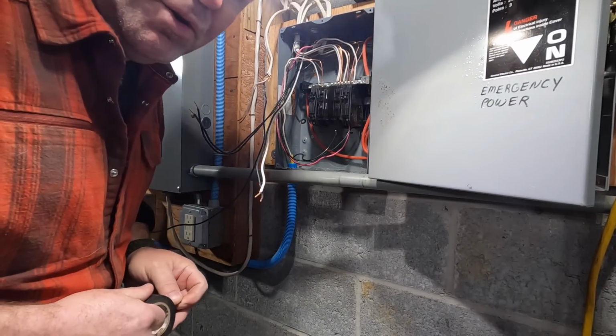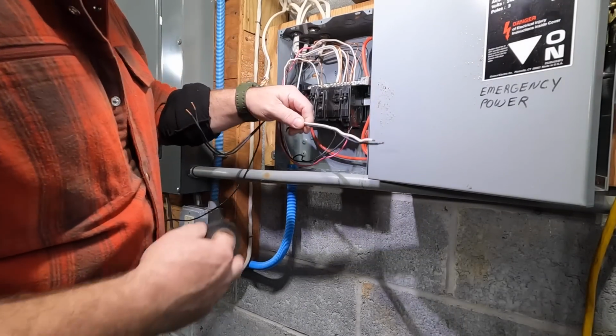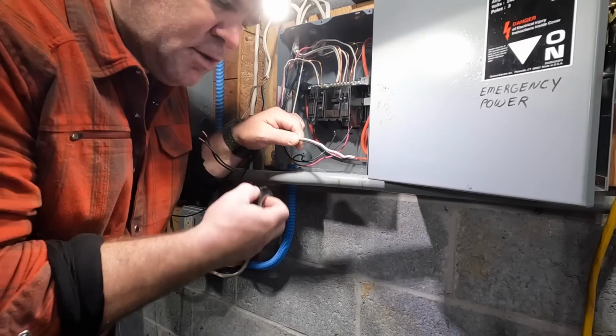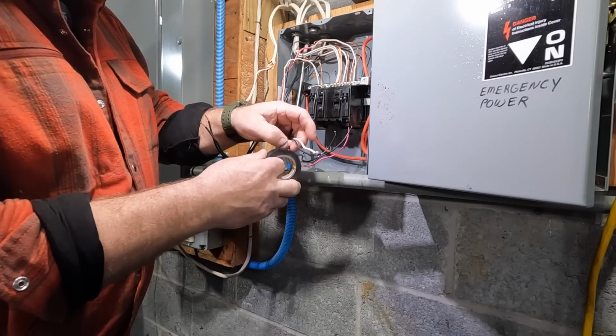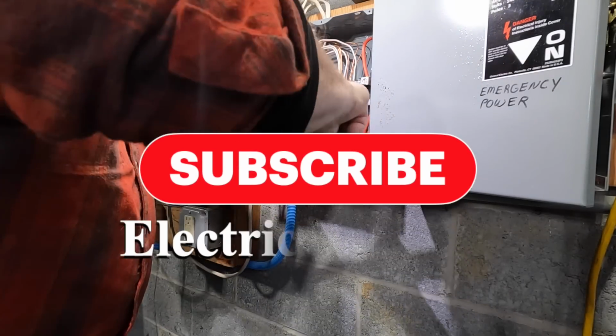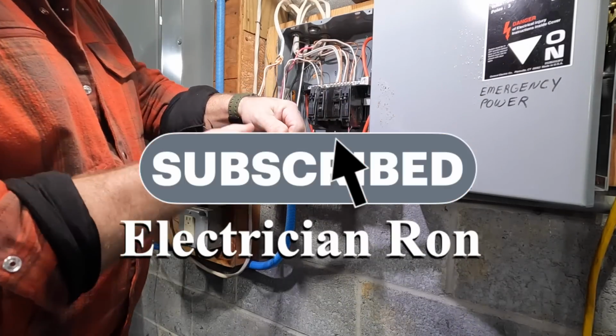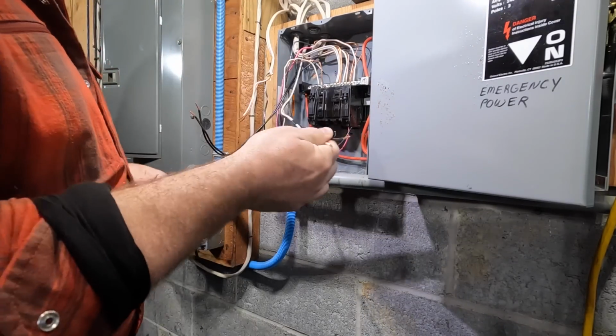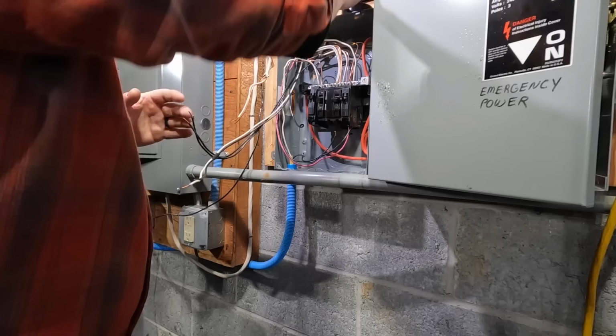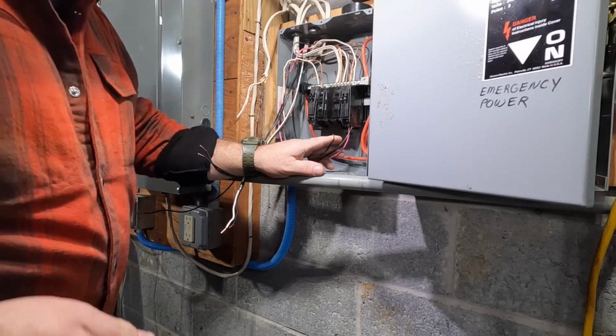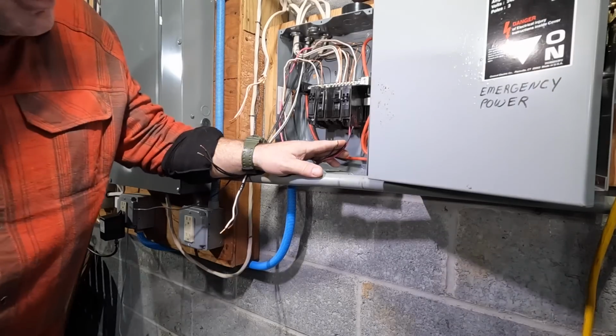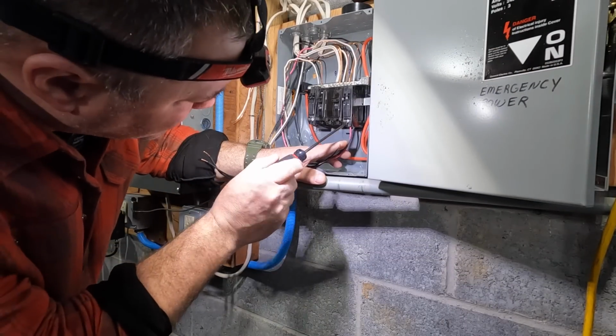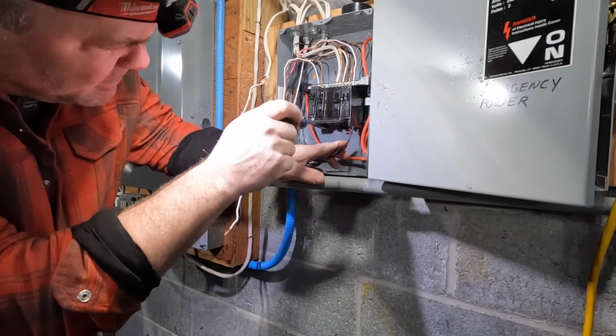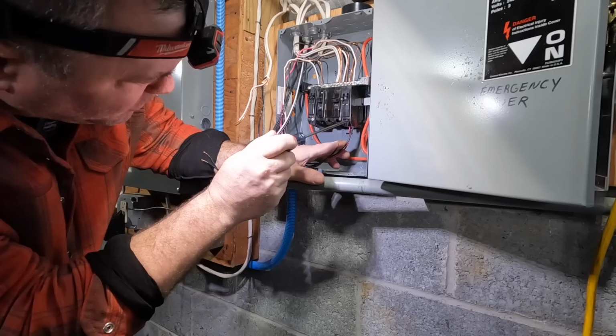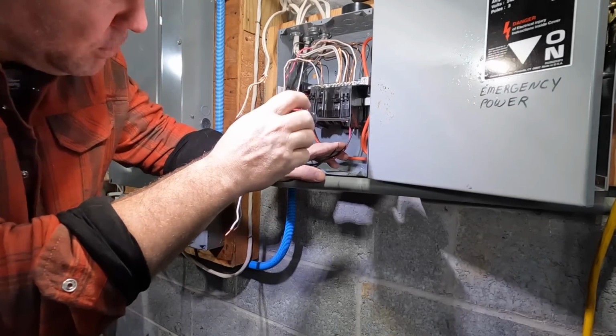One thing you should always do when you're taking circuits out of a panel, if you have a double pole circuit breaker, what I always do is just put both of the conductors together and just tape them together. When I put this back inside the new panel, I'll know that this is a double pole circuit. What is a double pole circuit? A double pole circuit is a circuit that has two poles. And in a single phase electrical service, you're going to have two poles, L1 and L2. That's what double pole is.